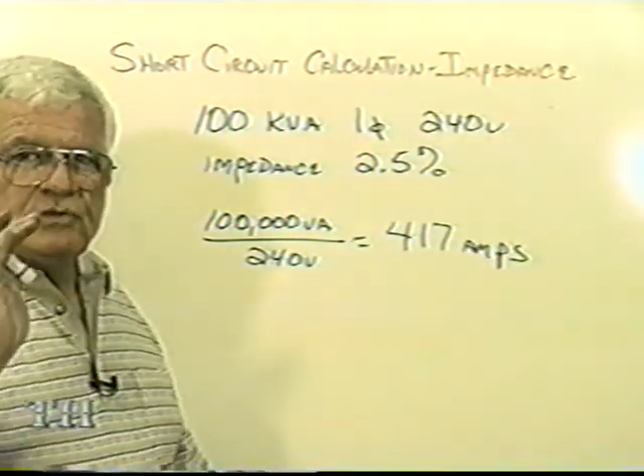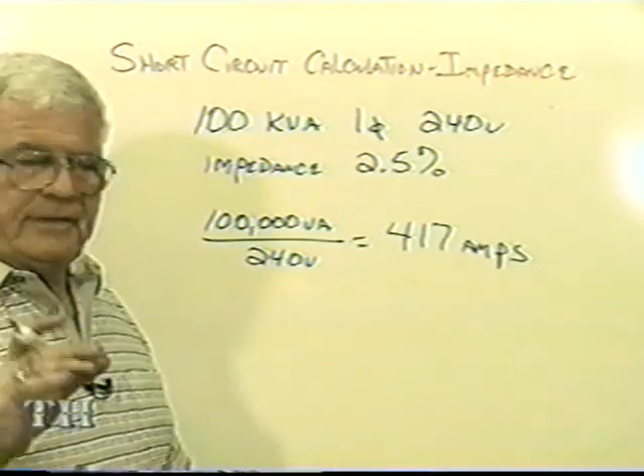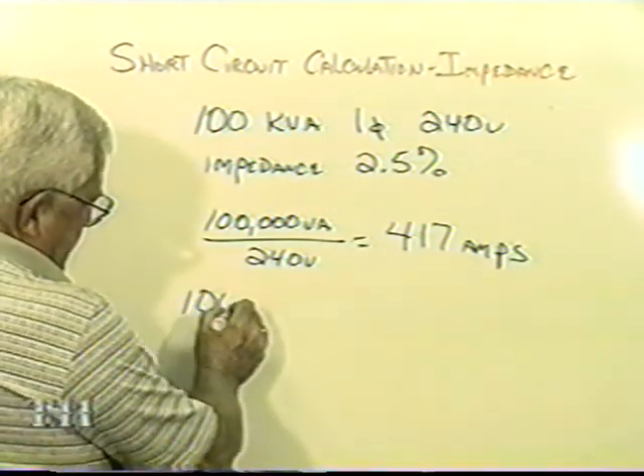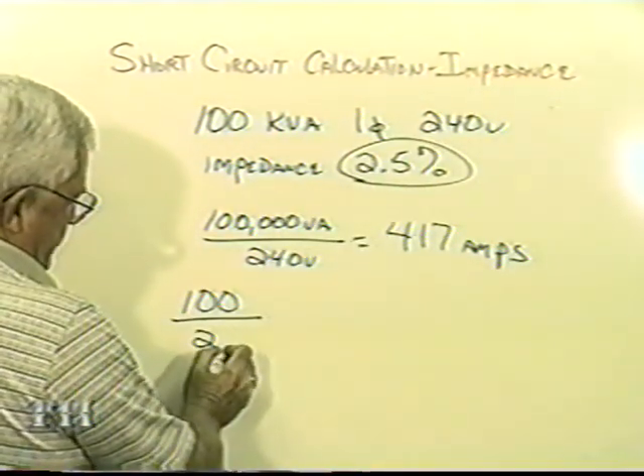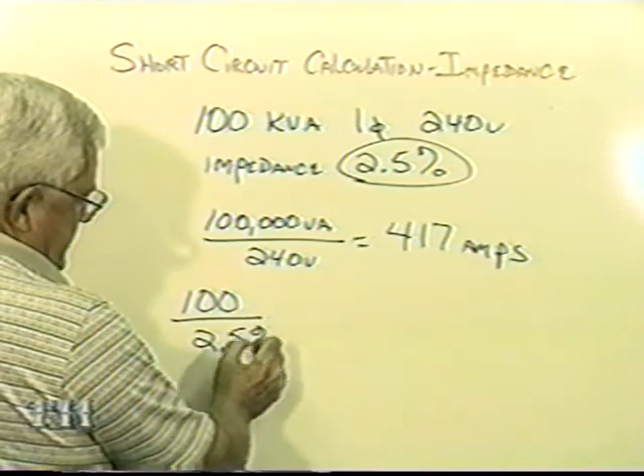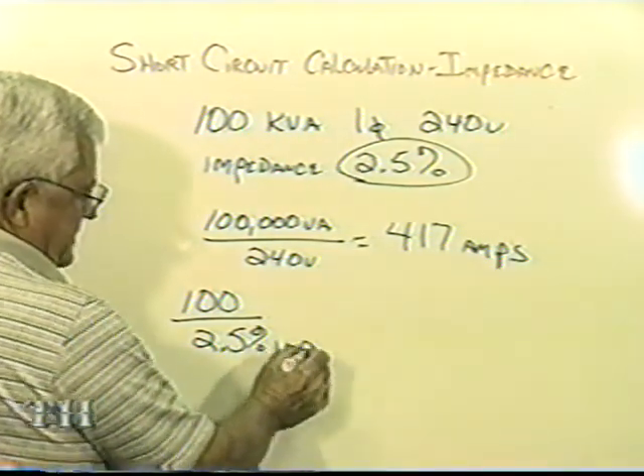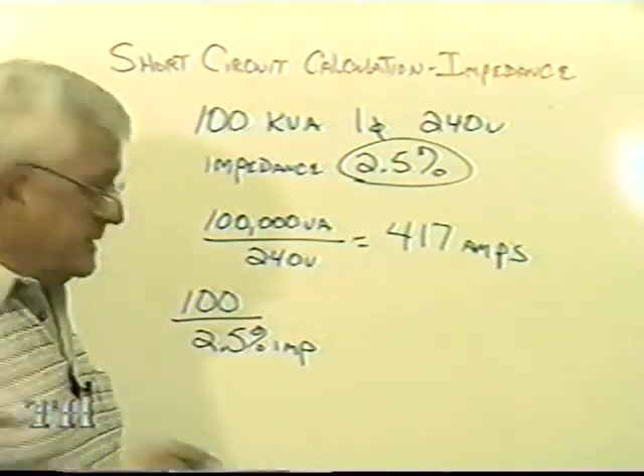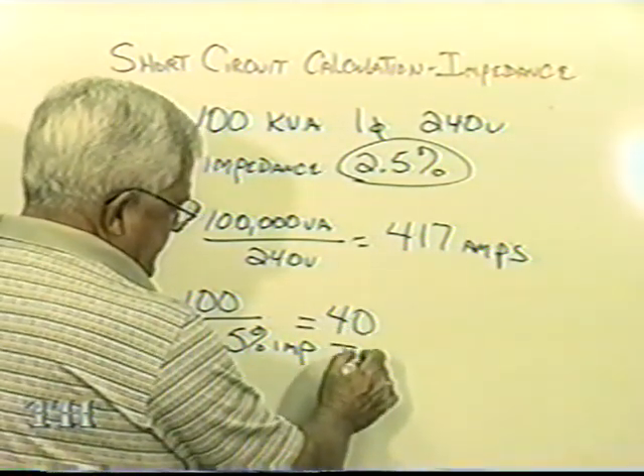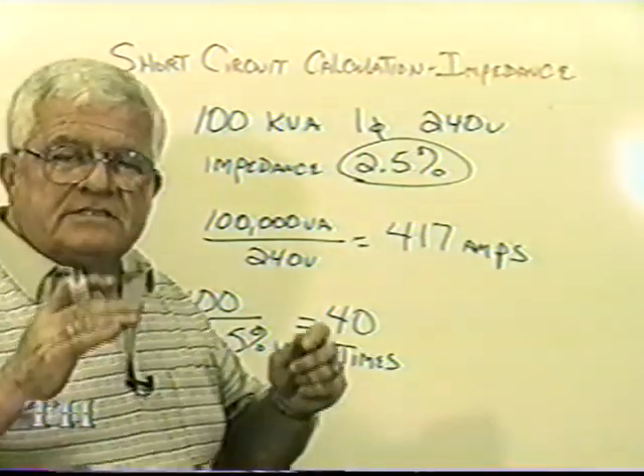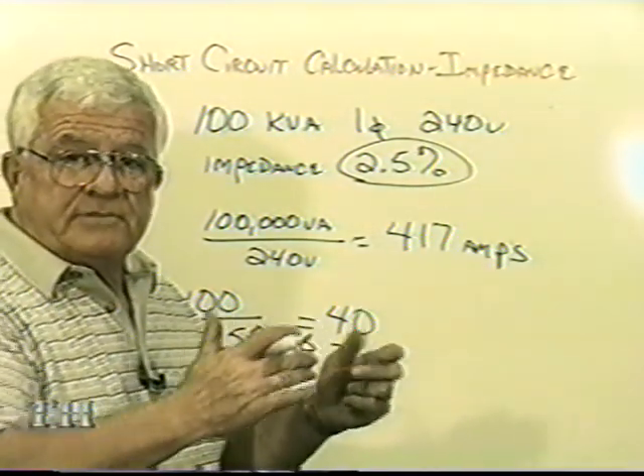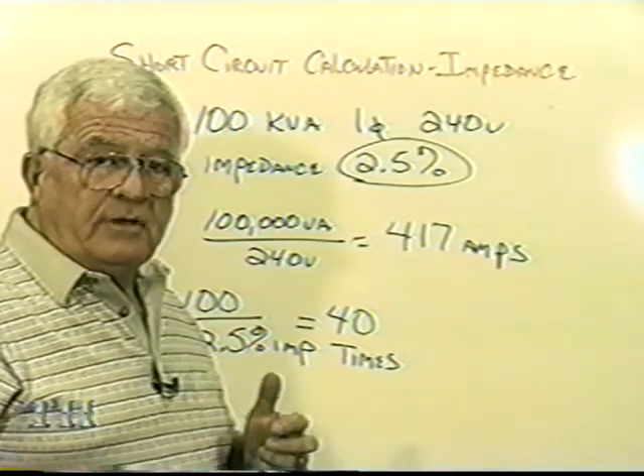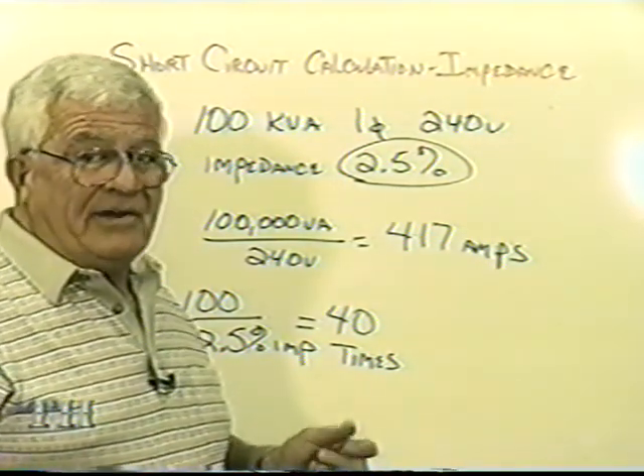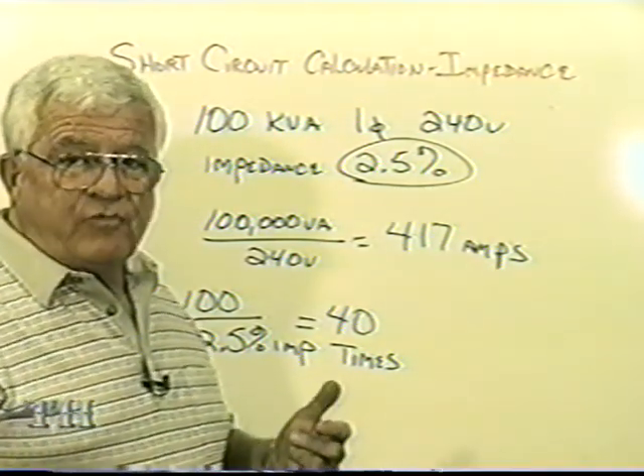Now, what you would do at this point, once you have the rated current, take that 100% that we did a moment ago and divide that by whatever impedance they give you. Here they're saying it's 2.5%. Now what happens is, this is going to come out to 40 times. In other words, as that impedance went down, like say it was 5%, now it's 2.5 on this transformer, then the available current is going to be higher. Before it was 20 times, now it's 40 times.